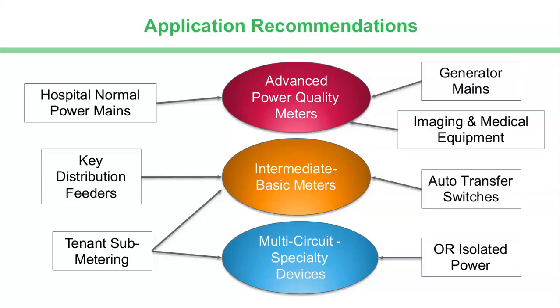And then, as I mentioned on the previous slide, there are also multi-circuit devices that are often used for tenant submetering. And we'll show some examples of that. But typically, if you've got a panel board or a switchboard, you've got the need to meter many circuits within that rather than having individual meters, there now are multi-circuit meters that can be applied.